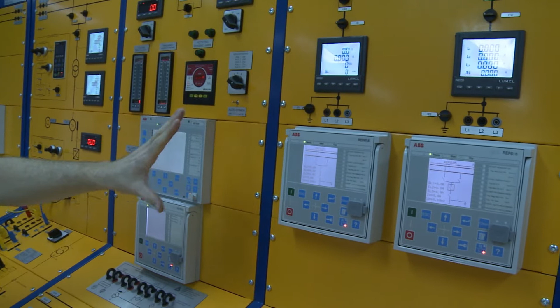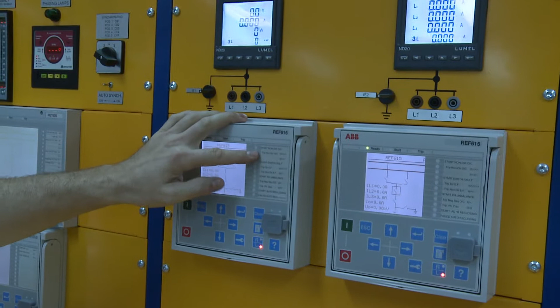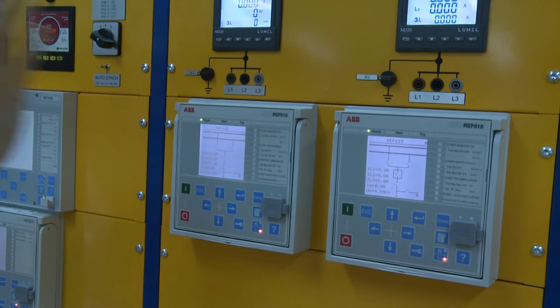Here we have our outgoing lines, two lines to choose from, which also have their own protections, feeder protections in this case. And here we also have overcurrent. We have a directional earth fault protection, so we can make faults on this side and faults on the back, and it should react for these ones, but not for these ones. That allows us to divide up into different zones. Negative sequence, we have phase discontinuity, so if the lines are cut, and also some auto reclosing. Is a reverse power relay good there? Reverse power, not in this one. We have the generator, not in this one either, but there is in the one that you are leaning on beside here.